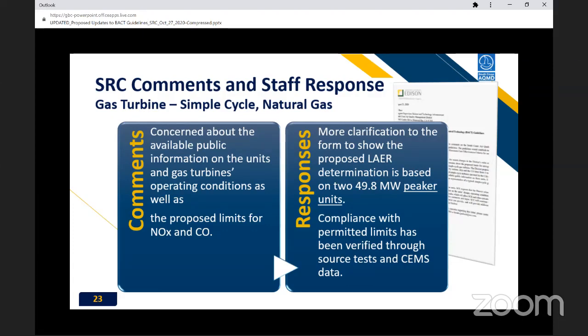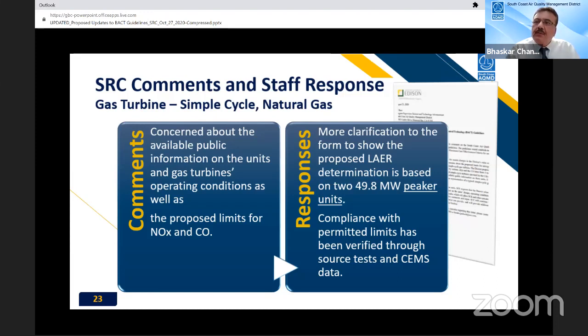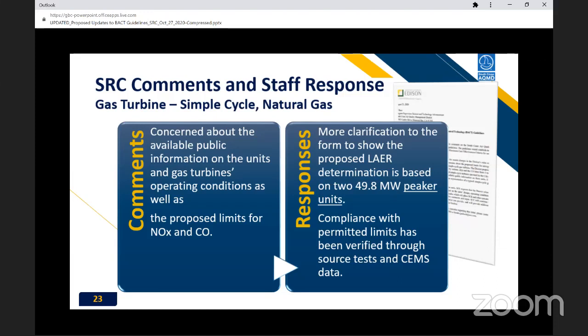No, typically to change out the catalyst, the unit has to be shut down, because they have to go inside and change the catalyst. That requires a unit shutdown, and that is very costly. So I just want to make sure that the limits in BACT apply for the duration of the life of the catalyst, whether it's 3, 5, or 6 years, and not just based on the initial performance test.